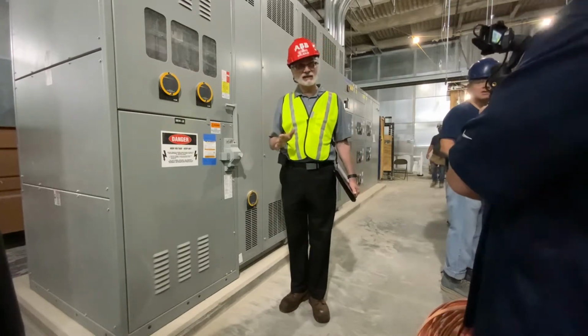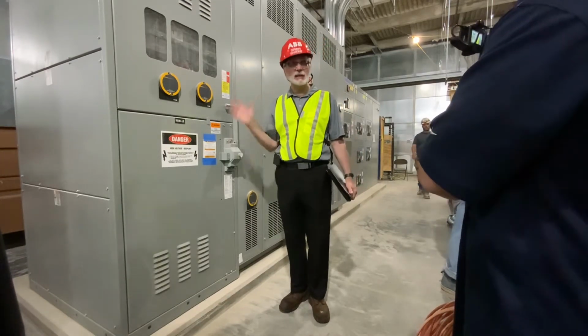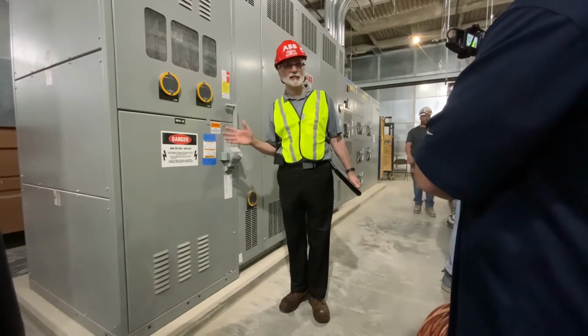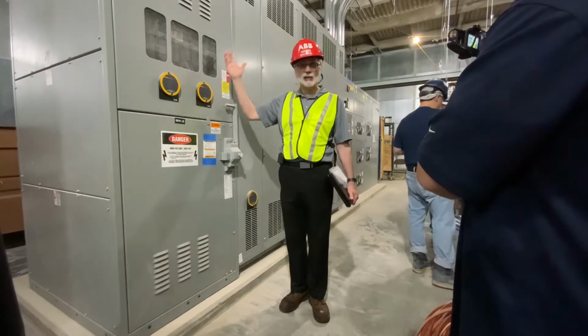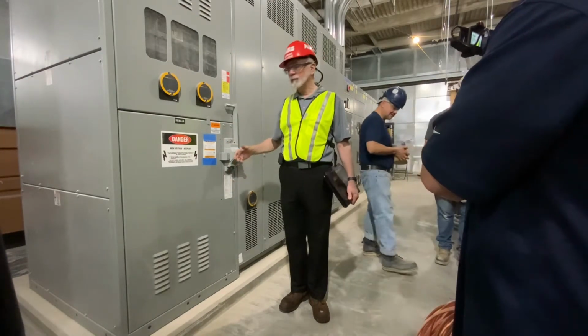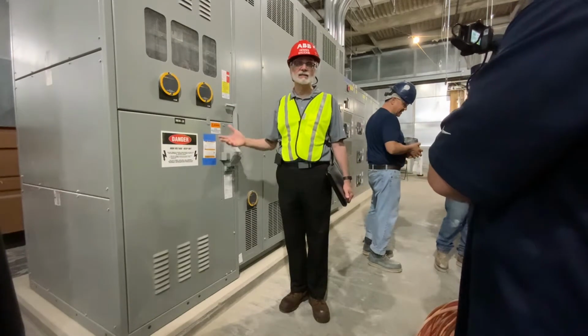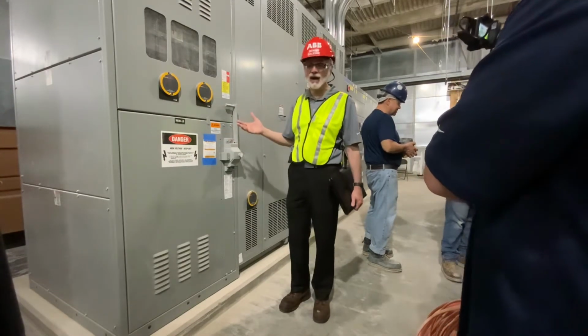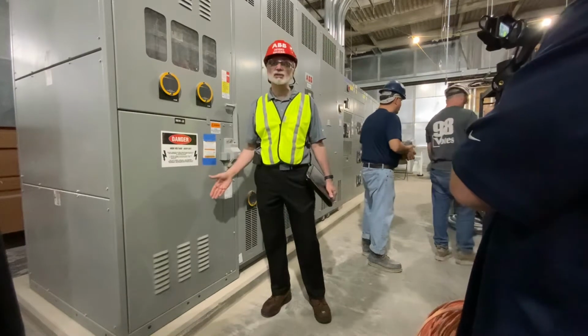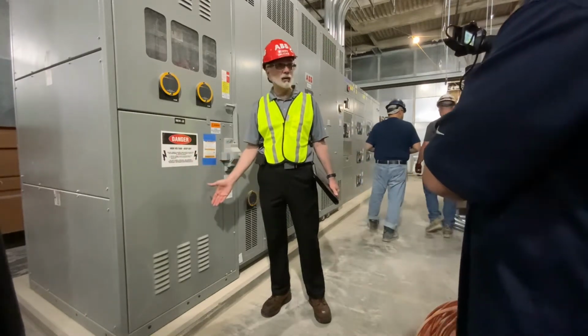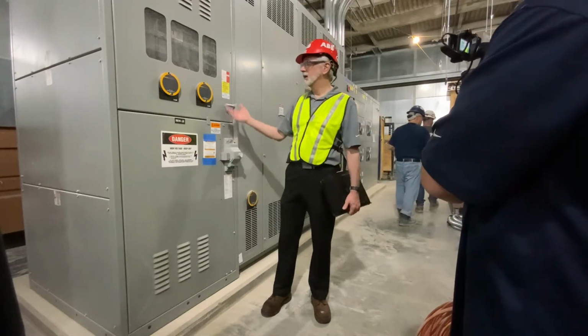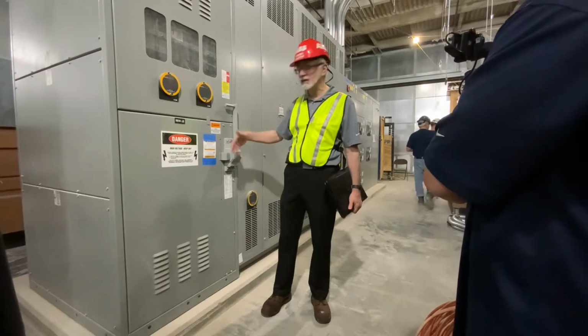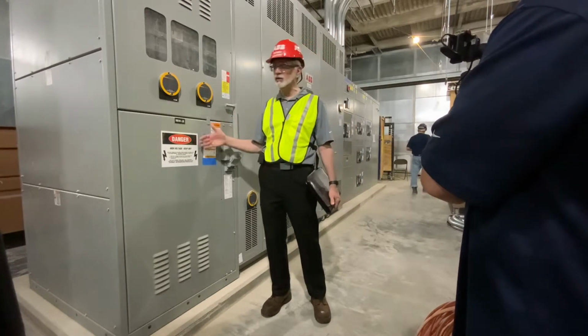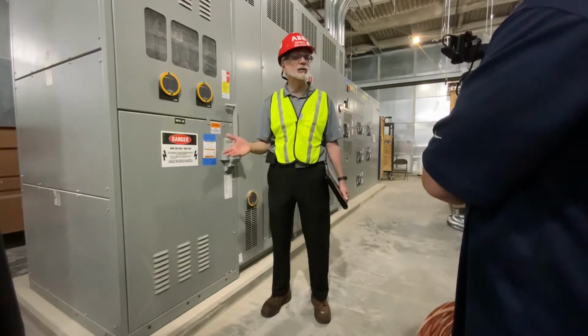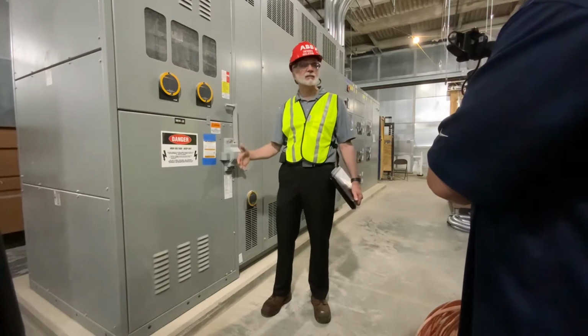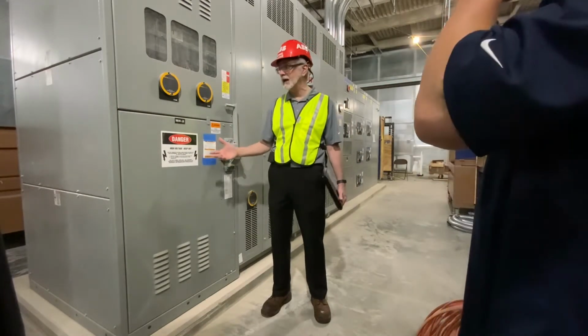From a service standpoint, this is even a simpler piece of equipment than what we talked about before. It's basically just got switches and fuses. So if you do experience some sort of interruption of power, you could potentially have a fuse blown out up here. So, after you de-energize the equipment, there's an interlock that prevents you from opening the door while it's in an energized position. So then you would check to make sure that the fuses are good or bad.